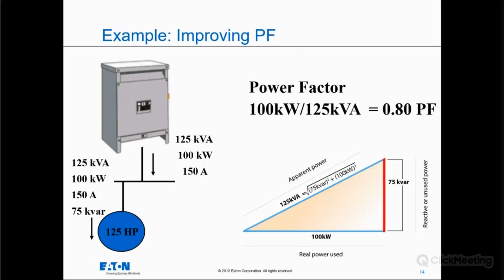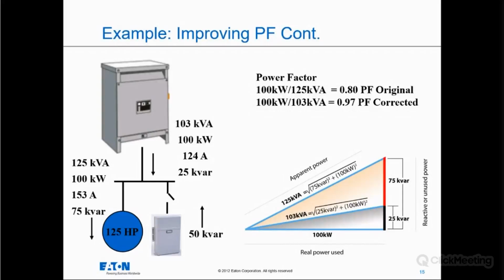Again, is there a more efficient, effective, and better way to do it? Yes, there is. You can come in and locally put a 50 kVAR capacitor there by the motor. This will now feed 50 kVAR to the motor, so I'm only pulling 25 kVAR through the system. So if we look now over to the right, we see that the work is still the same. The motor still is going to generate 100 kW of real work. But again, we're supplying 50 kVAR locally, so now we're only pulling 25 from the utility. And we see our hypotenuse, our total power drops from 125 to 103 kVA.